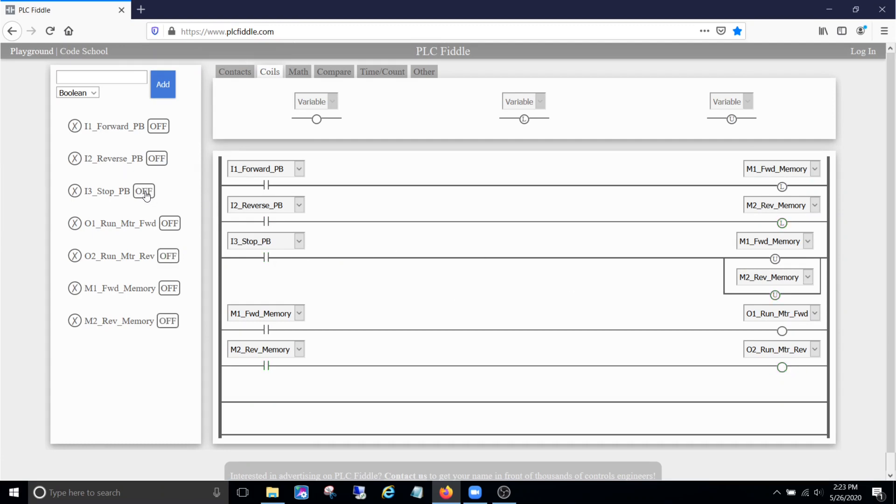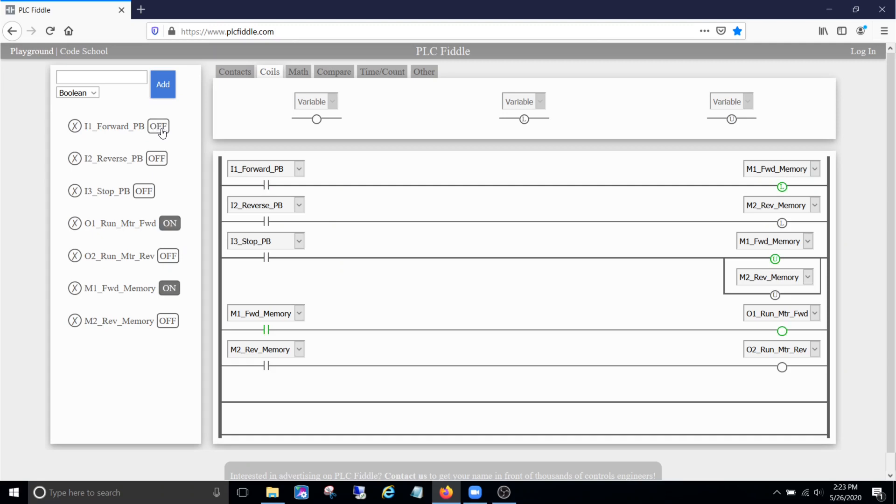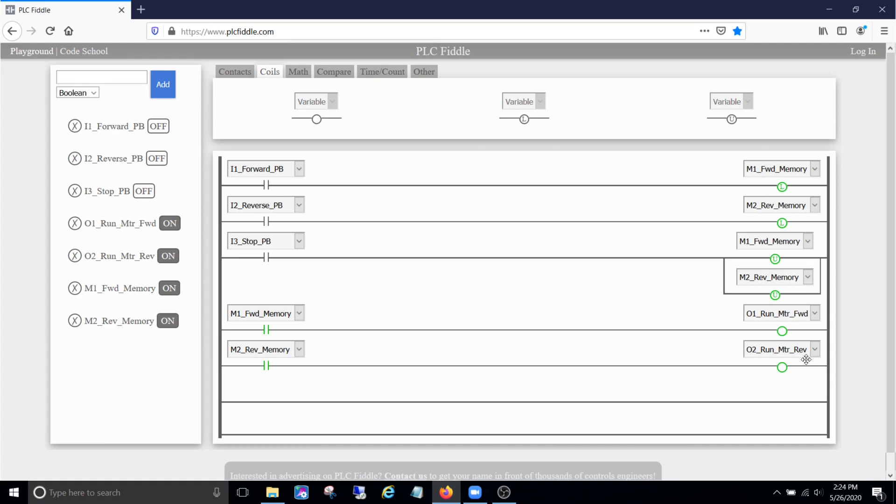Now one thing. So that's most of the scenario, that's what we said we were going to do. One topic that I want to bring up is if this is one motor that can go either direction, the way we have it programmed right now, it can run or the outputs for forward and reverse can come on at the same time. And that's not good for the motor, right? It can't run both directions at the same time. So we need to do something so that only one of these outputs can come on at a time.